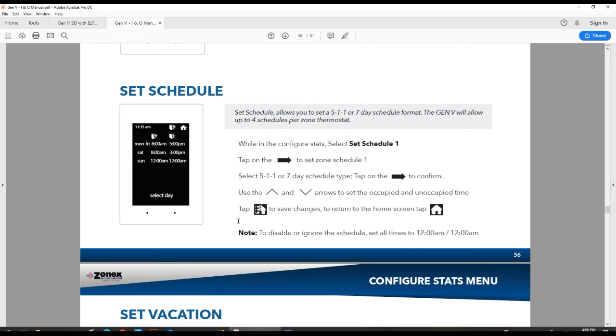And if you want to ignore a particular day or keep a day in unoccupied mode, say Sunday in this case, because nobody was there, we'll go ahead and set the time for the same, so 12 a.m., 12 a.m. This will ignore the schedule on Sunday, keep the system in unoccupied mode, and will return to normal occupancy the next day of occupancy. So in this case, Monday at 6 a.m.